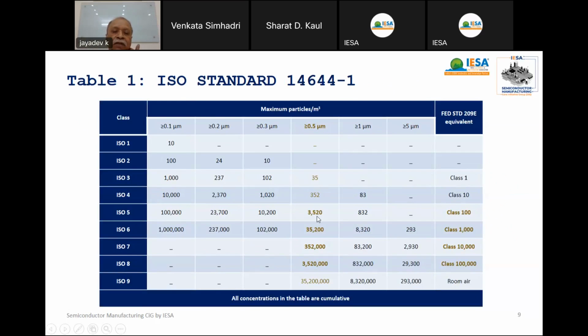So normally I will just try to explain with reference to 0.5 microns. Very easy to explain this. See, these 0.5 micron particles in 1 cubic meter of air. Normally we count 0.5 micron particles in 1 cubic meter of air. We are referring to a cubic meter. So if you want ISO 3, there will be 35 particles of 0.5 micron in 1 cubic meter. That is equal to ISO 3.